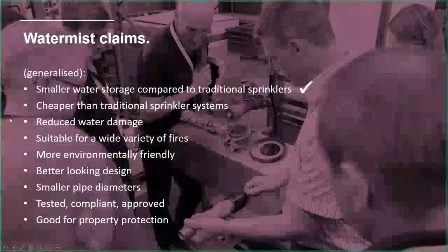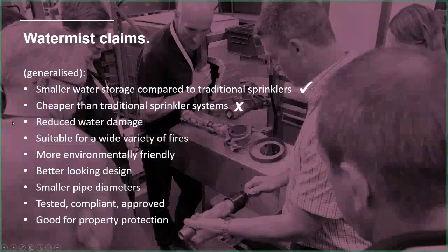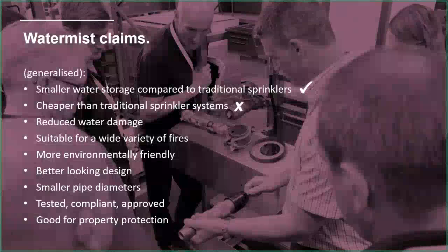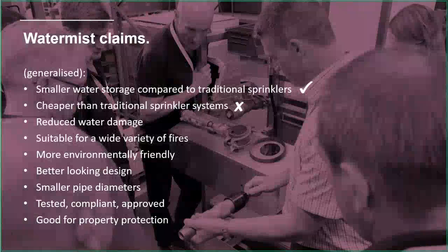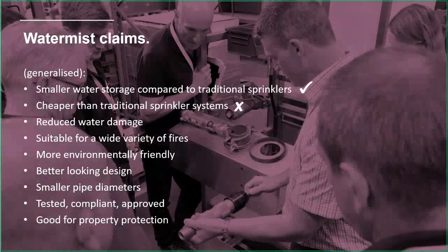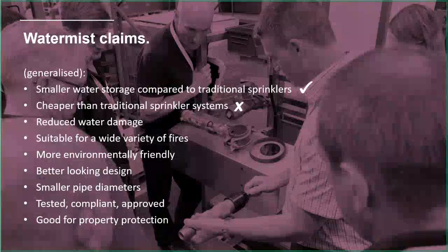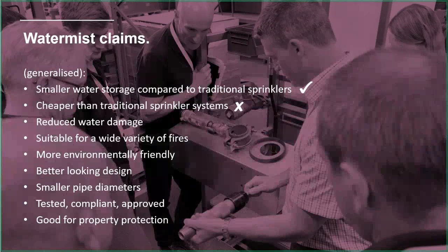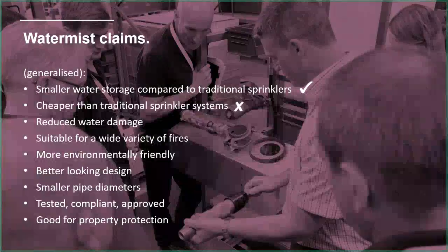Next one: cheaper than traditional sprinkler systems. To that, I would say no. Mist systems are very different from manufacturer to manufacturer, and style to style, so their price is going to vary. Sure, you might find a mist system which is slightly cheaper than an equivalent sprinkler system, but some are going to be a little less, some a lot more. Some mist systems are going to be a lot more expensive than sprinklers because you're basically paying for bespoke, specialist equipment.